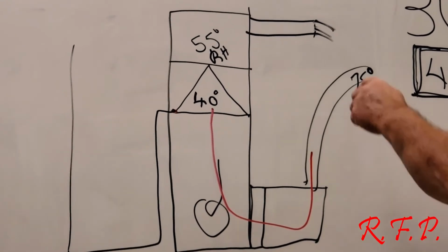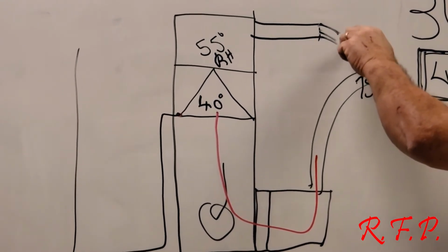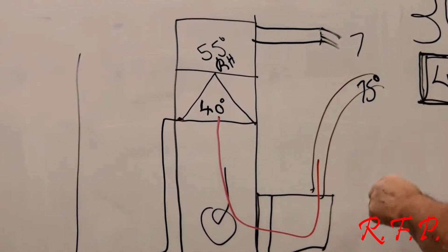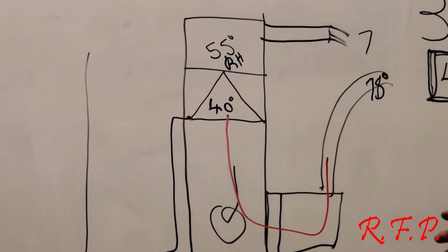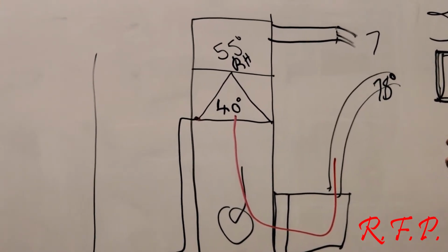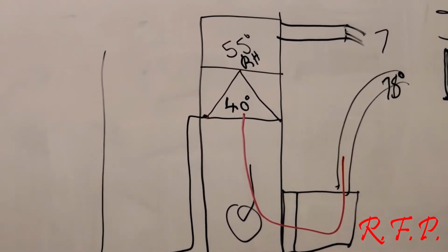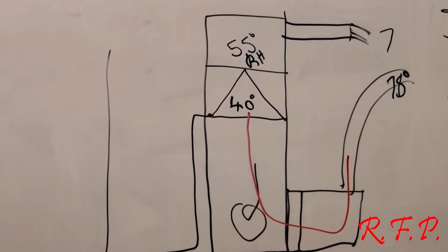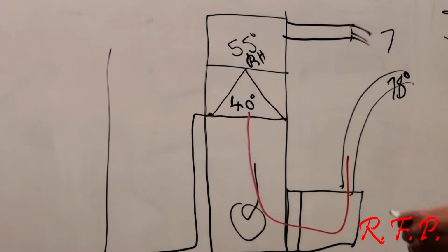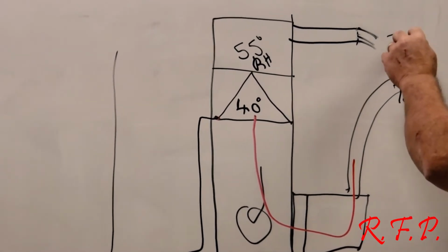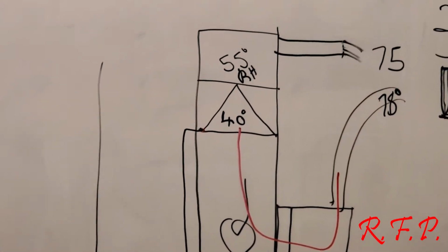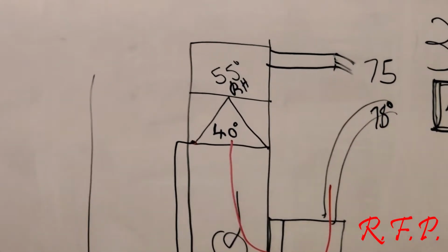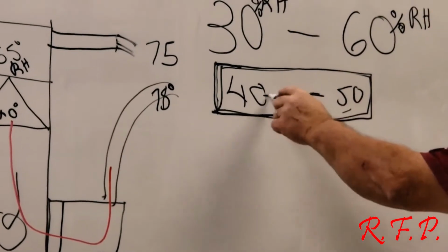When it mixes back with a 75 degree room temperature, that's probably more like 78 going in. We're trying to achieve 2 or 3 degrees change in the room. The thermostat wouldn't even be on at 75 unless it's at the end of a cycle. When we mix it back with 75 degree air in the room though, our relative humidity drops back down somewhere between 40 and 50%.